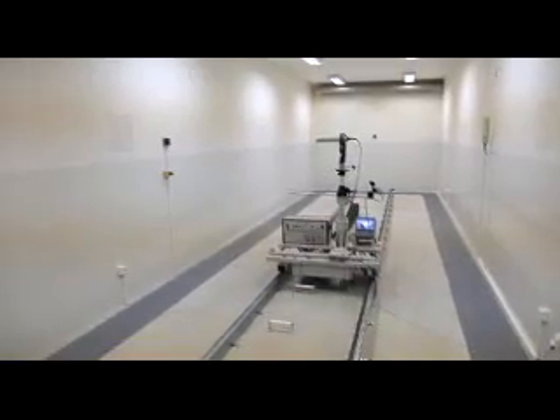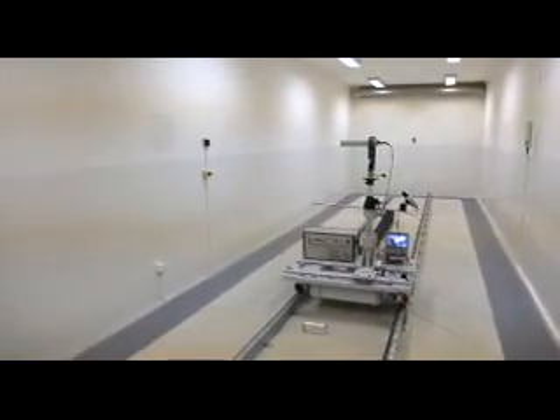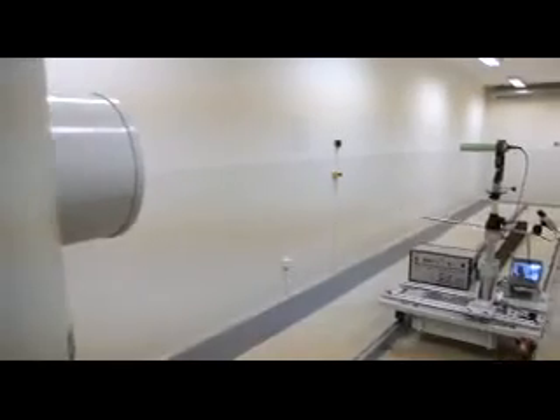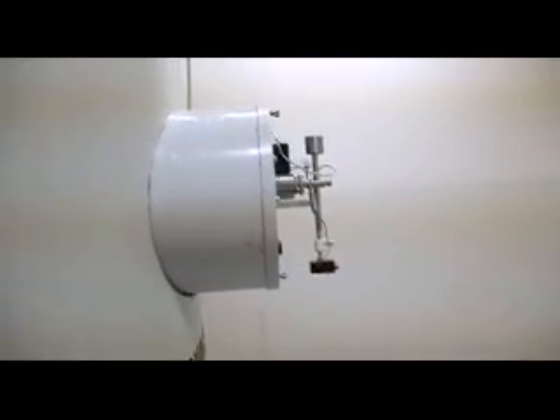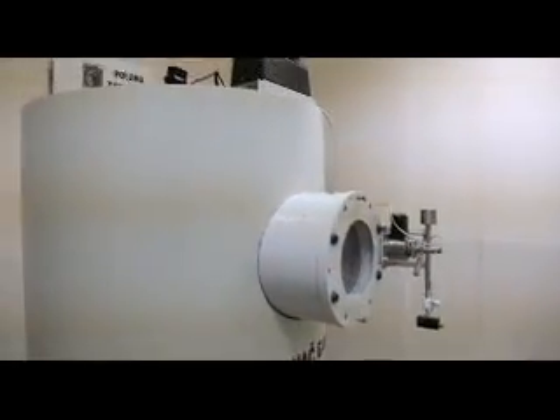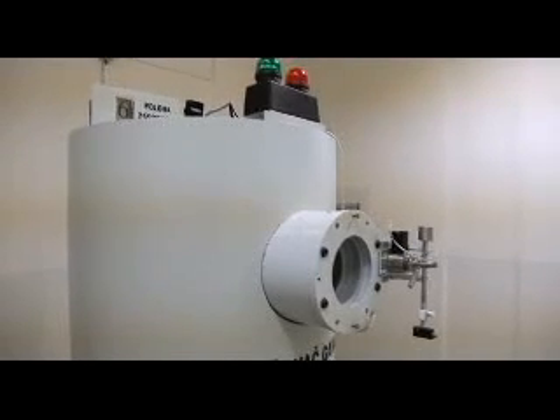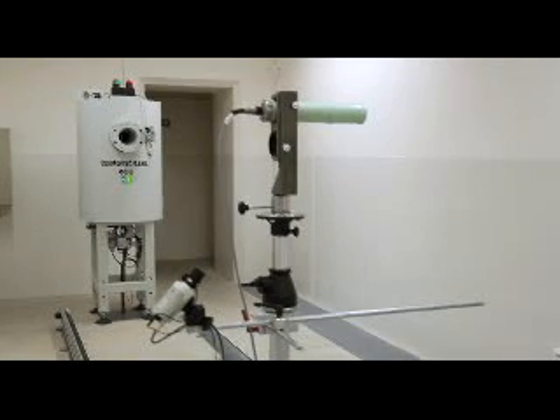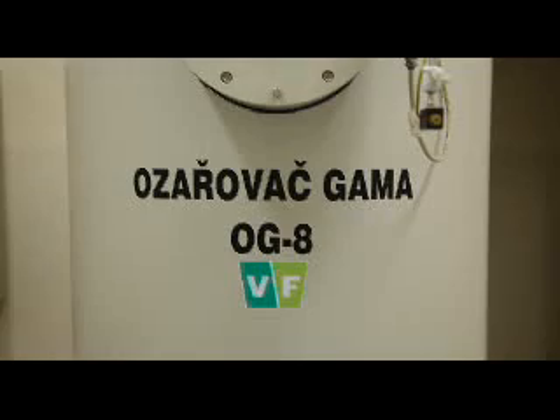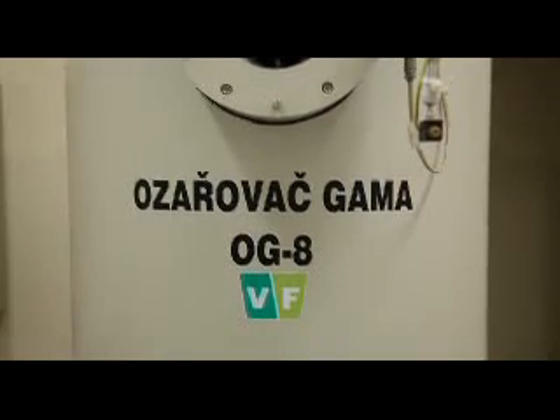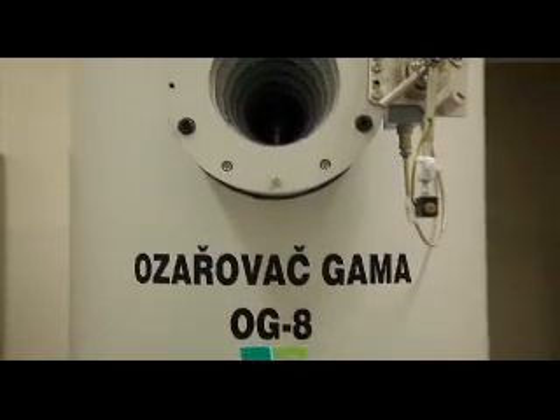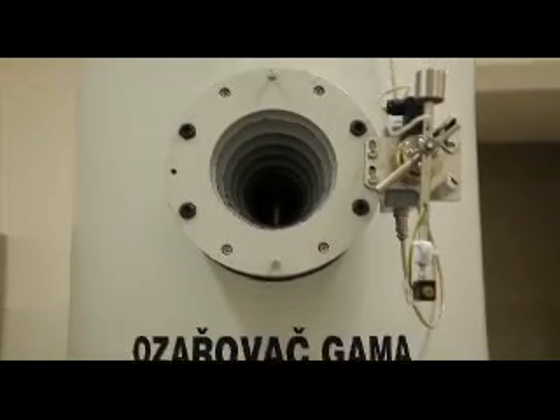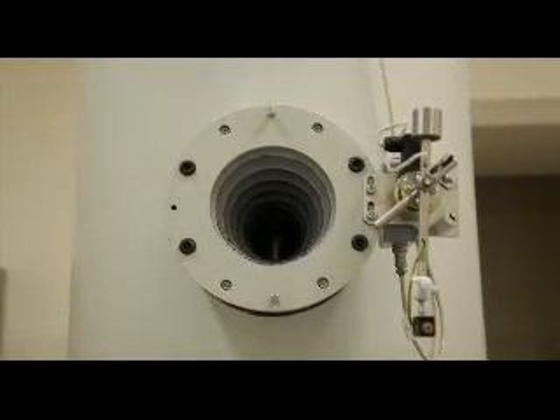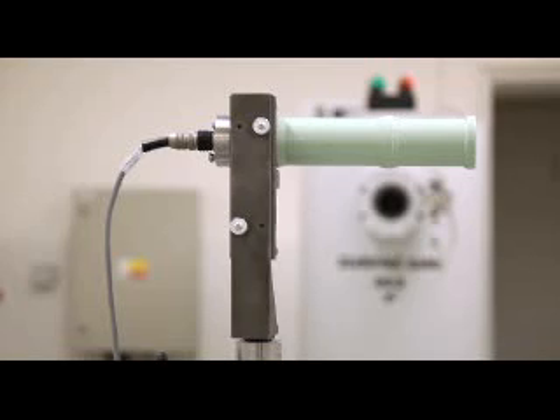The calibration facilities are situated in a custom-designed room which ensures sufficient shielding of the surrounding environment. One part of the calibration laboratory is the calibration room, where the OG8 irradiator is to be found. The irradiator, loaded with suitable sources, is able to produce gamma radiation beams in the range of tenths of micrograys per hour up to grays per hour.